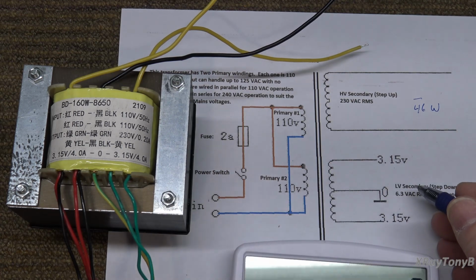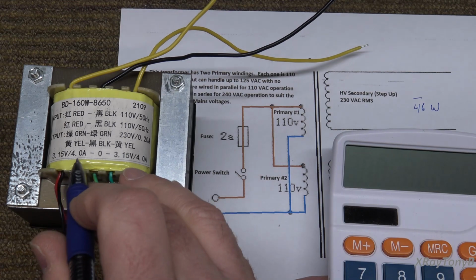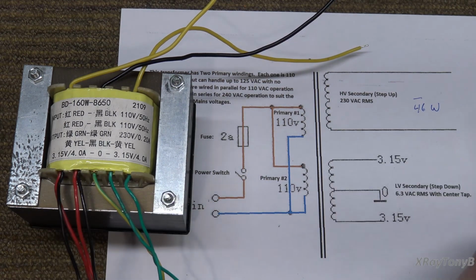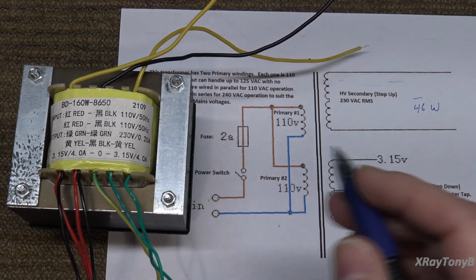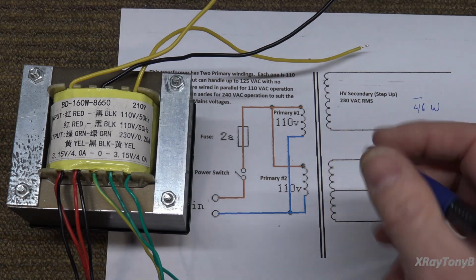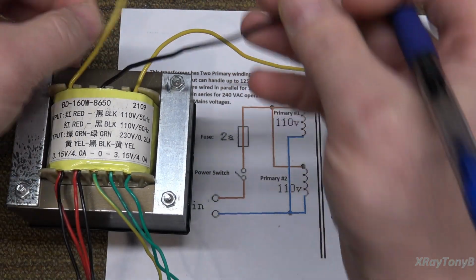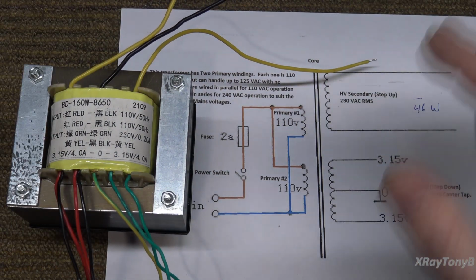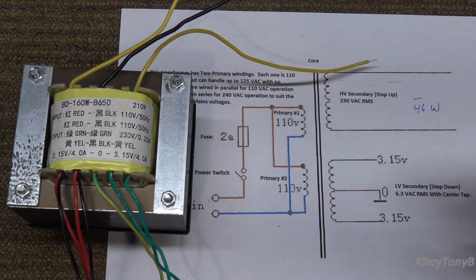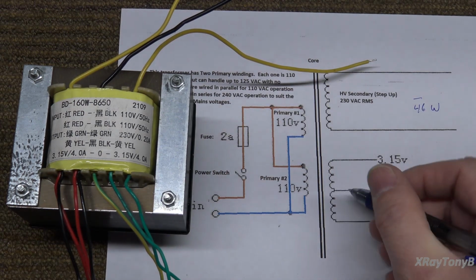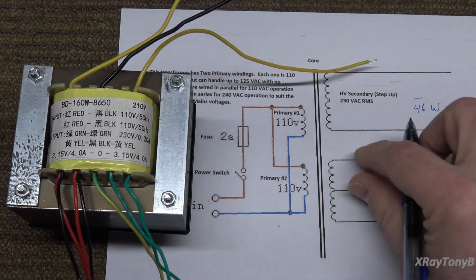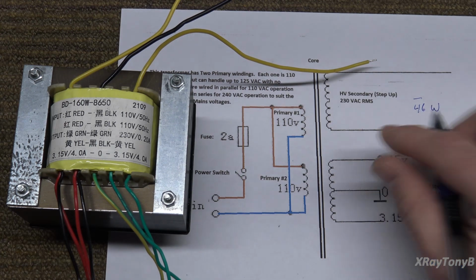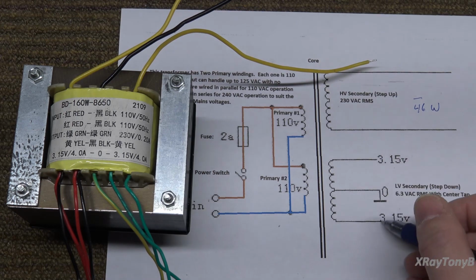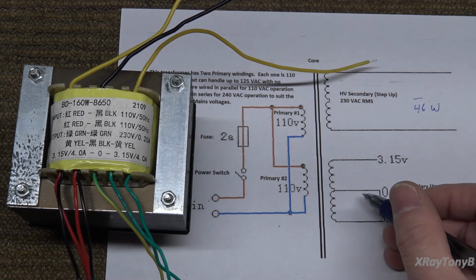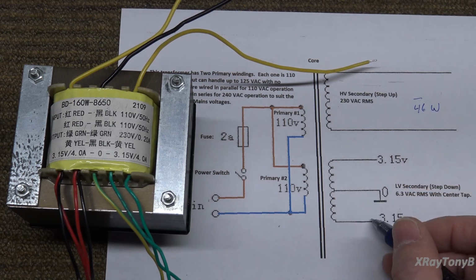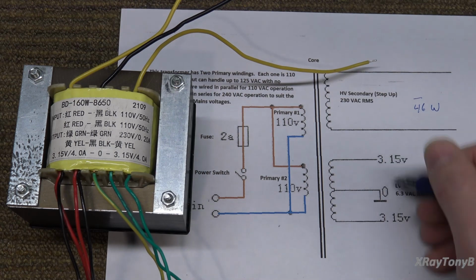Also, if I look at this secondary, it's rated at 4 amps. So you have 3.15 volts, and remember, this has what's called a center tap. So all they did is halfway through those windings, they connected a wire, which is this black wire, and they connected it to the center. And why they do that, we'll learn later on, especially when we get into designing the whole power supply. But if you measure from the center tap, since it's halfway down, you'll get half of the total voltage of the winding. So from here to here is 6.3 volts, but from here to here is 3.15 volts, and from here to here is 3.15 volts. It's half of the total voltage.